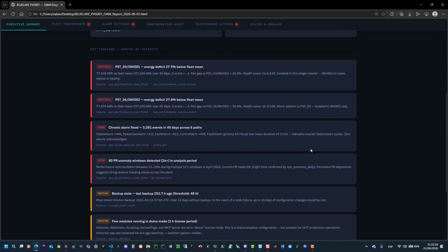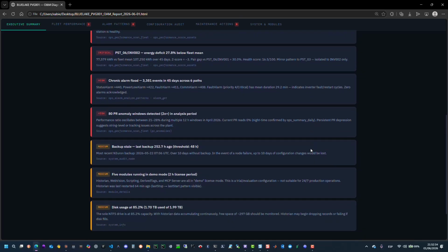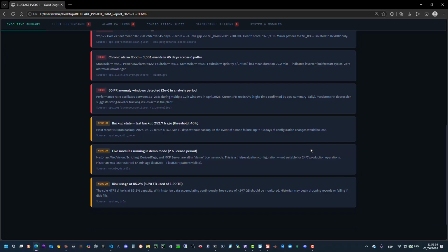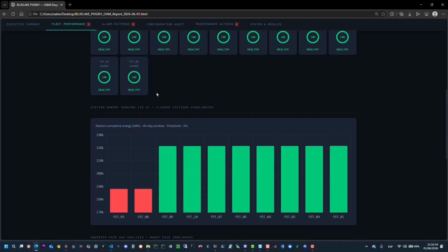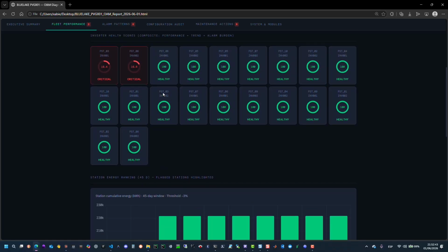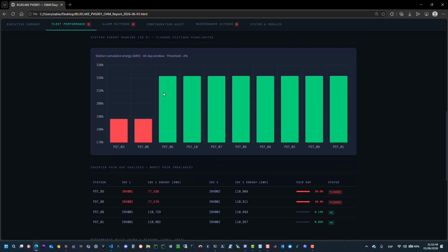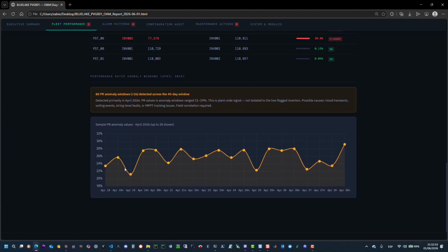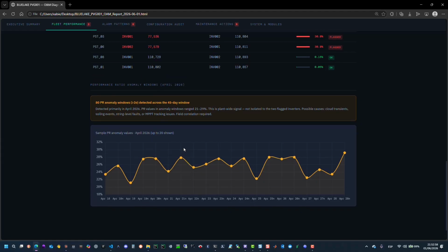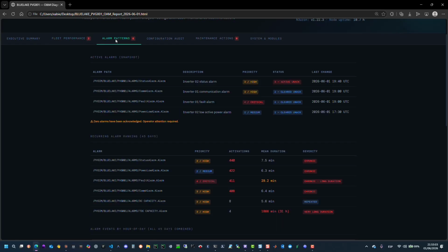What makes this more useful is the comparison against the paired inverters in the same power stations. The paired inverters are healthy, so the issue does not look plant-wide. It looks isolated to 2 specific inverter units. The report also estimates the business impact. Each affected inverter produced roughly 33,000 kilowatt-hours less than its healthy peer during the analysis window. At fleet level, this represents an estimated energy loss of approximately 66 megawatt-hours. This gives the maintenance team a clear priority. Start with those 2 inverters.